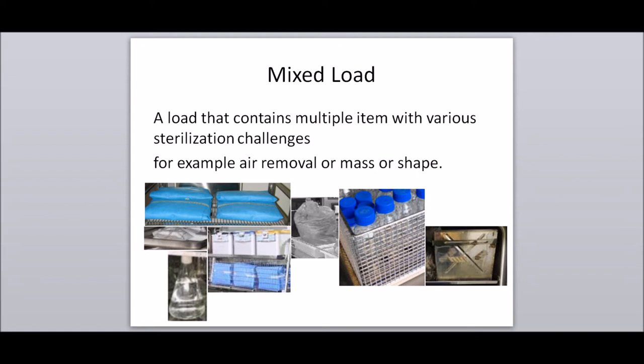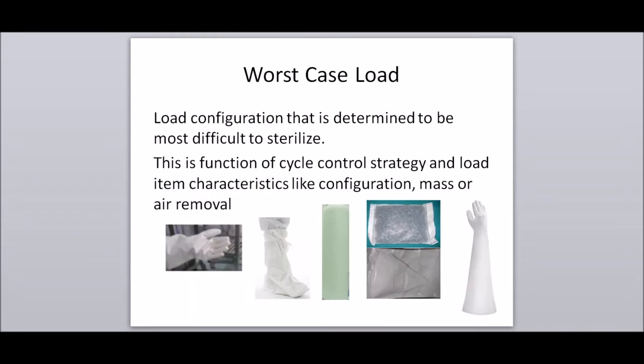Mixed load: a load that contains multiple items with various sterilization challenges, for example air removal, mass, or shape. Worst case load: the load configuration determined to be most difficult to sterilize. This is a function of the cycle control strategy and load item characteristics like configuration, mass, or air removal.